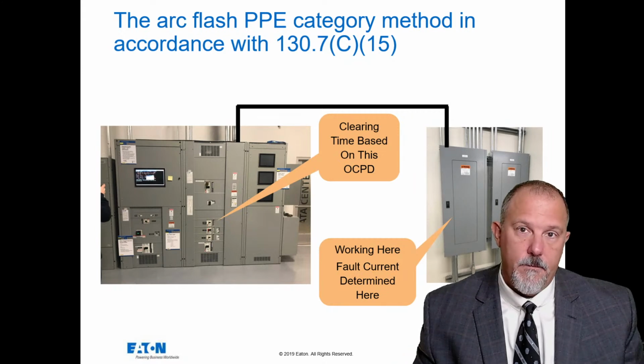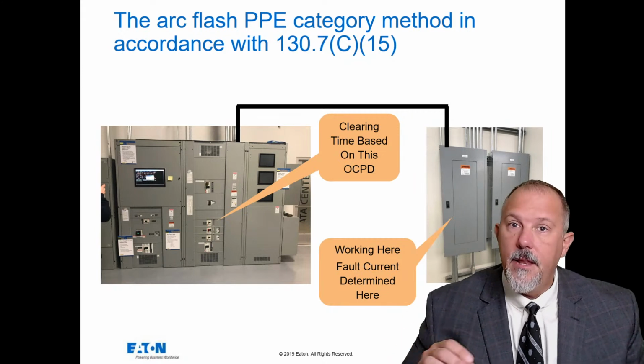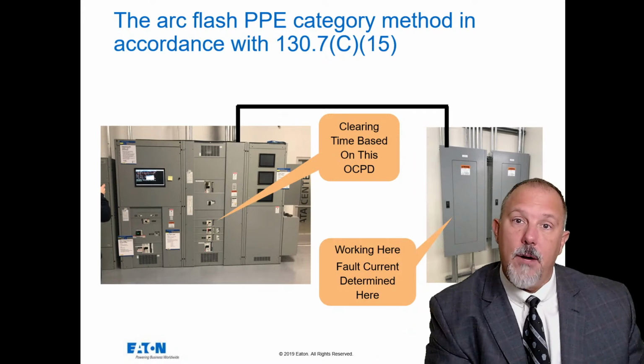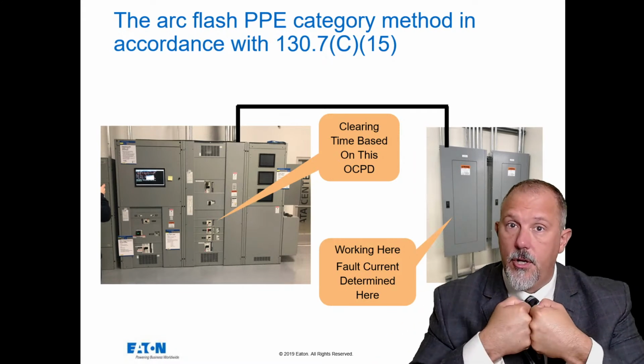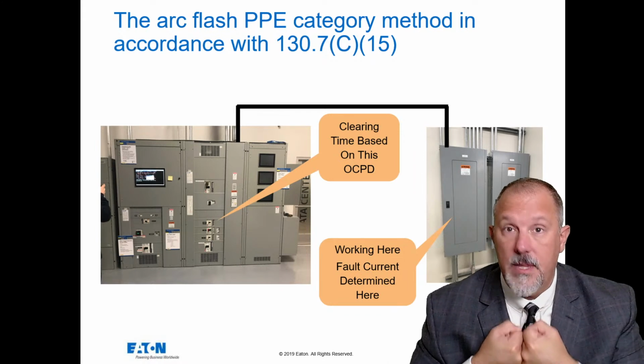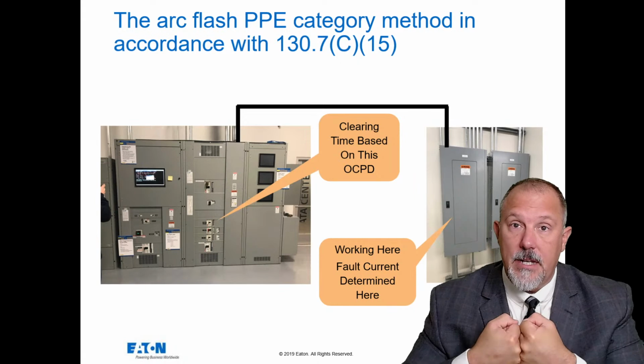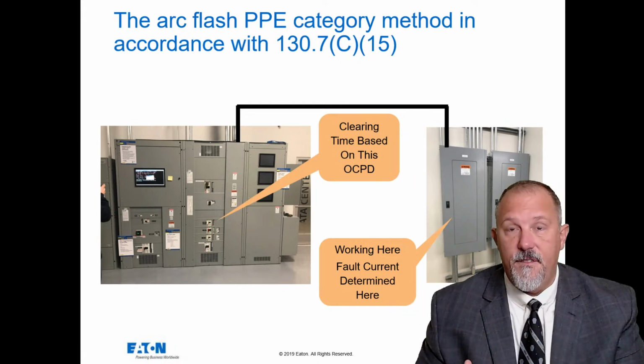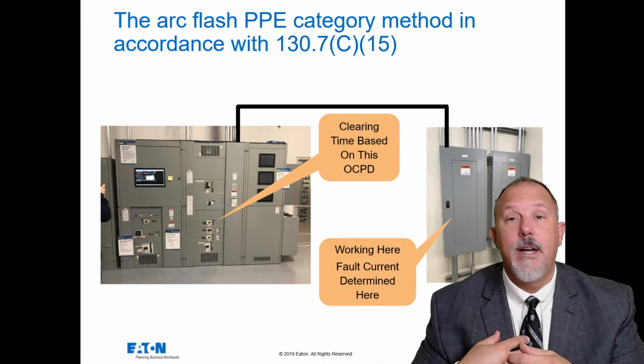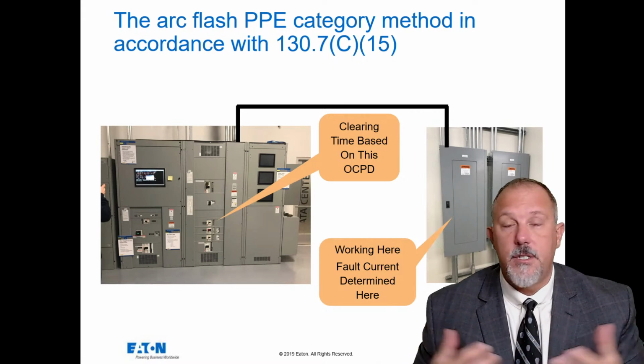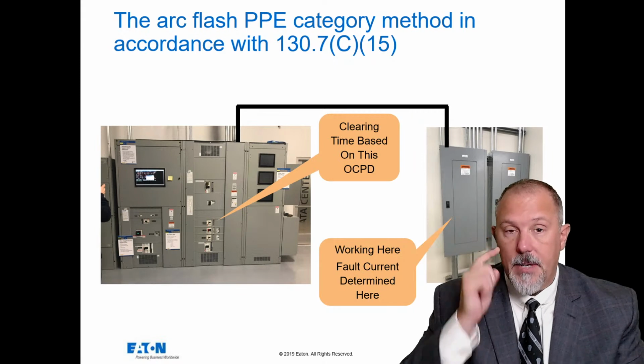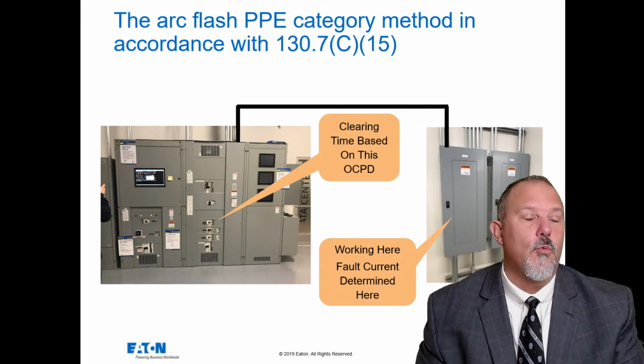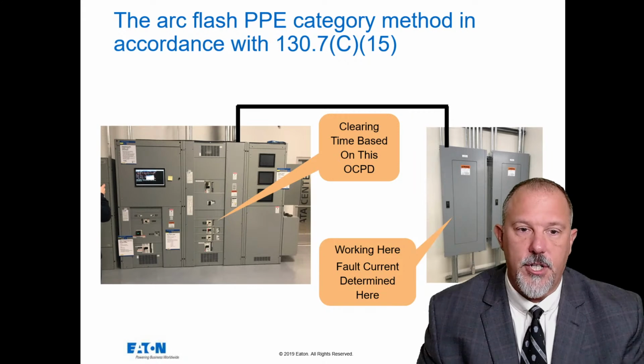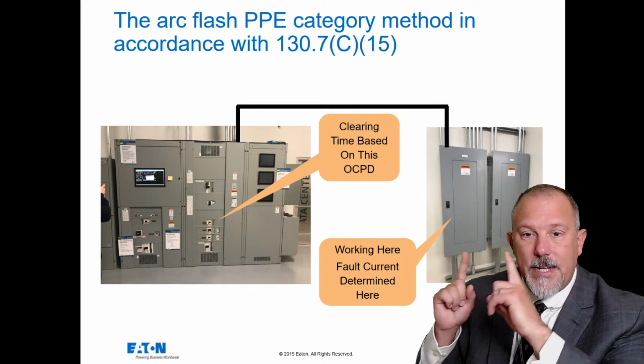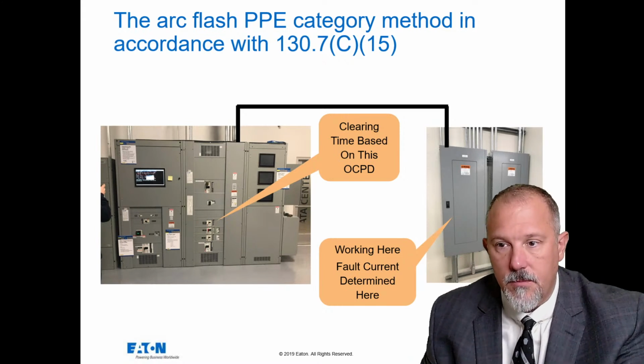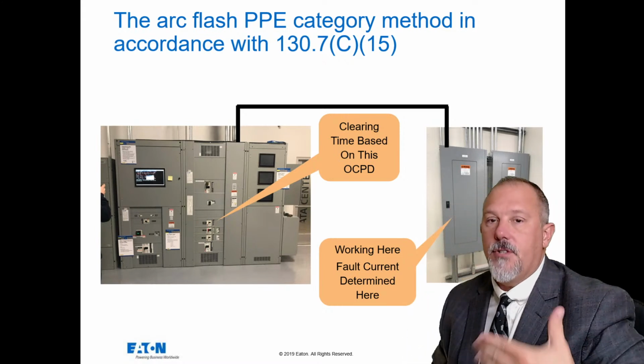All three 800 amp devices, but very different in the amount of energy that they'll let through, because that power circuit breaker can hold those contacts closed for up to 30 cycles. Think about that. Up to 30 cycles. One cycle is enough to give you a heat and pressure to just do some damage. But 30 cycles can really turn into a lot of incident energy. And if I'm doing justified energized work here, and I use that term, justified energized work, because that's an important thing to understand.